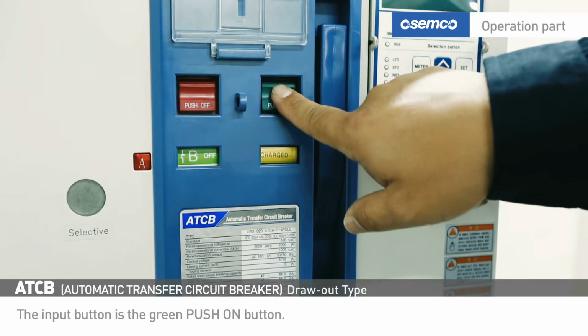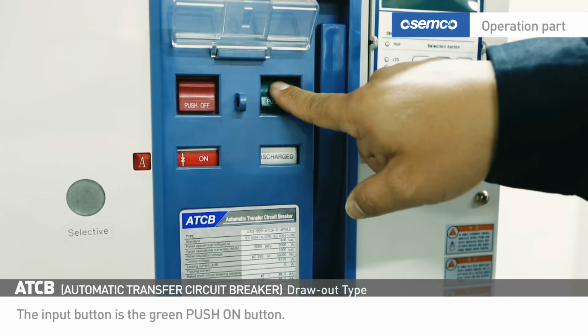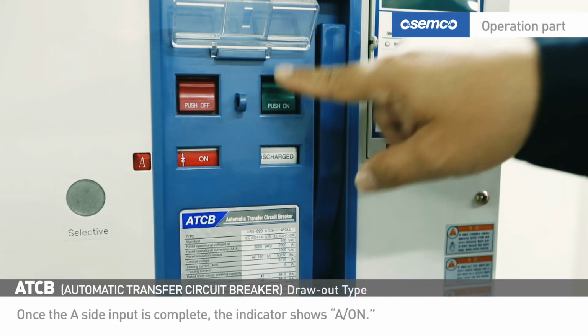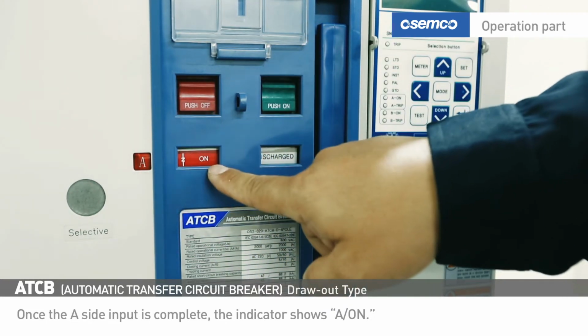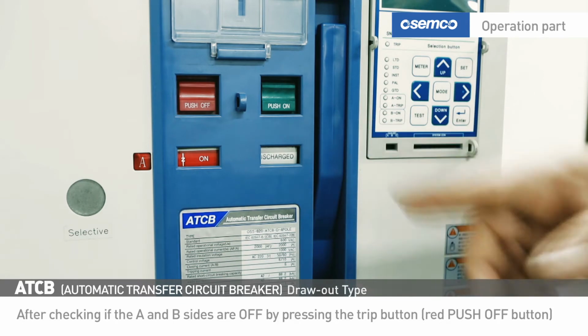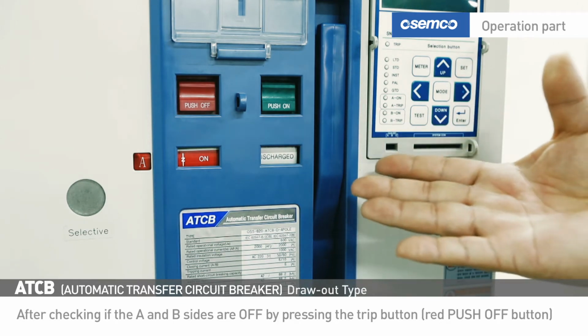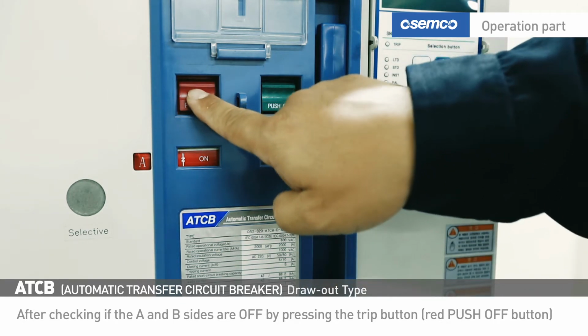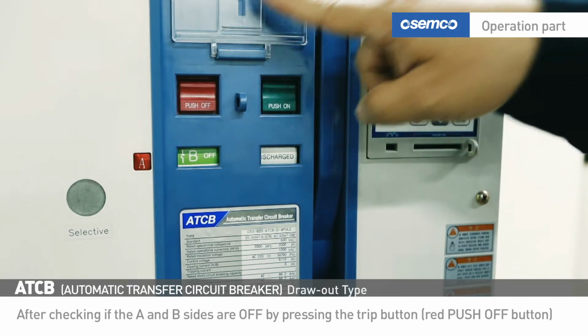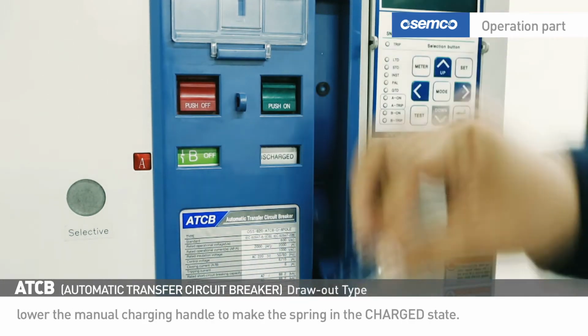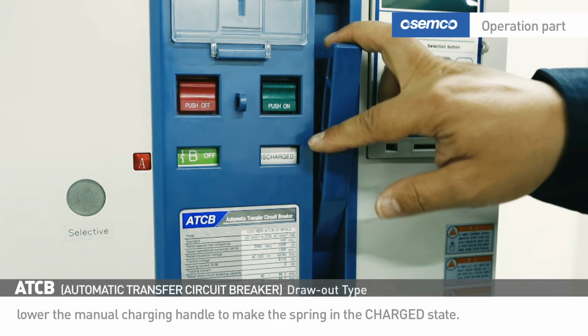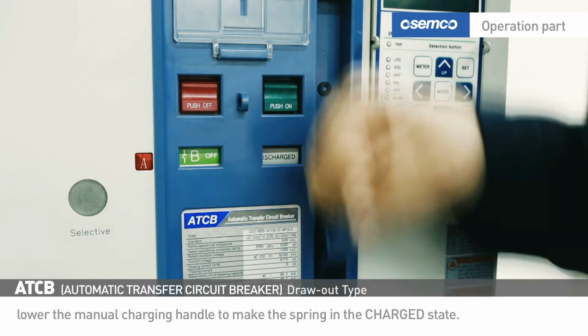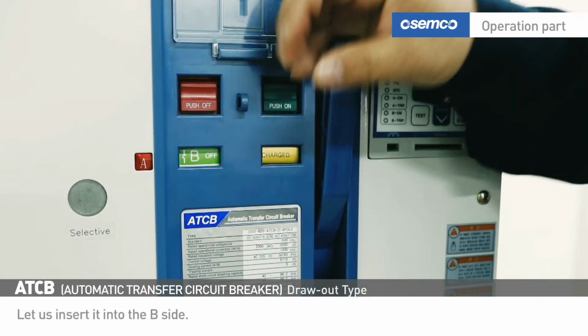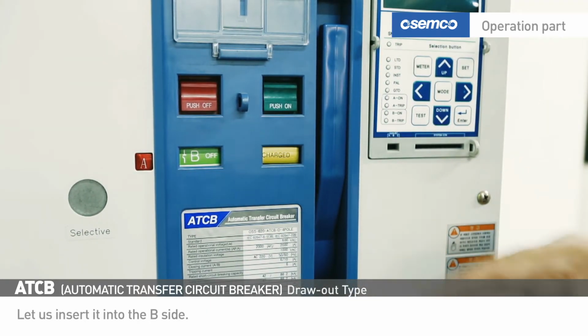The Input button is the green Push-On button. Once the A side input is complete, the indicator shows A on. After checking if the A and B sides are off by pressing the Trip button, red Push-Off button, in the A side input state, lower the manual charging handle to make the spring in the charged state. Let us insert it into the B side.